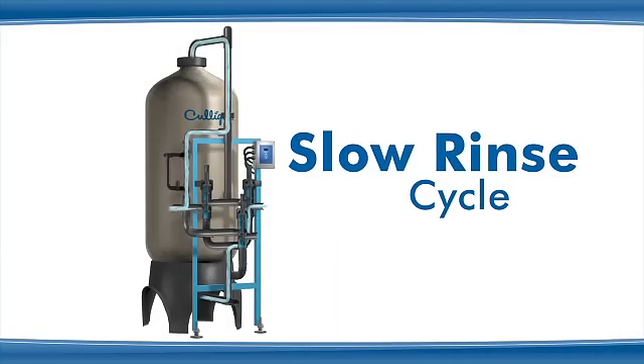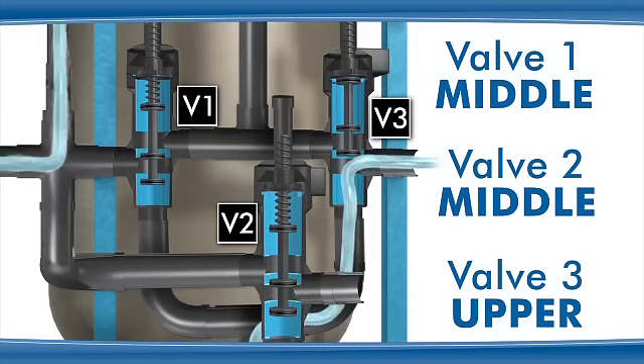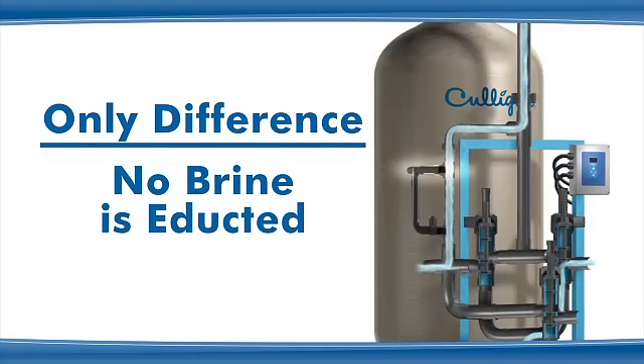For the slow rinse cycle, the valves are in the same positions and behave in the same way as the brine draw cycle. Water flows through the media bed and exits through valve 3 to drain. The only difference is that no brine is educted.